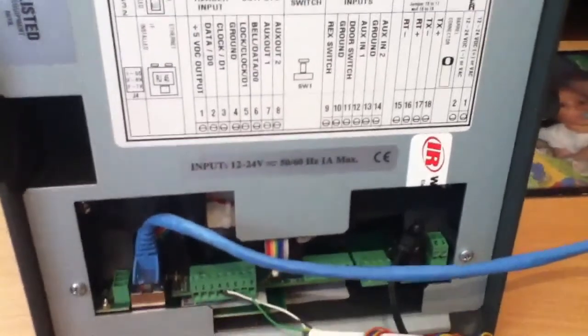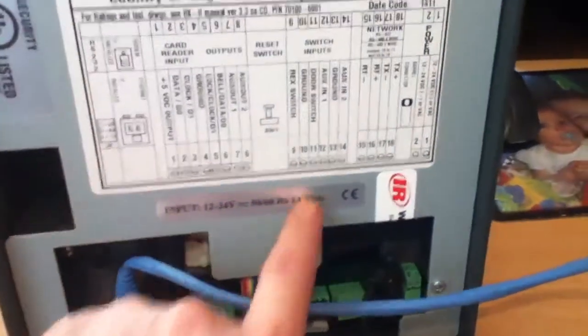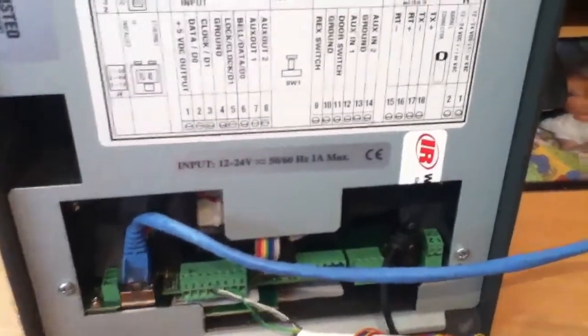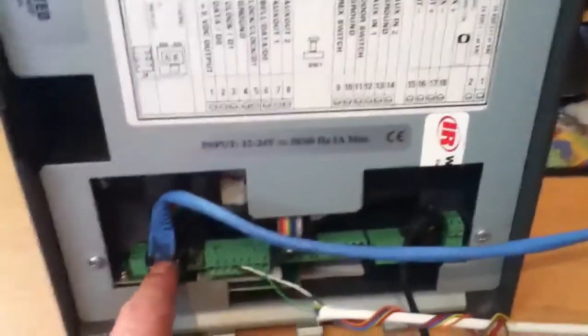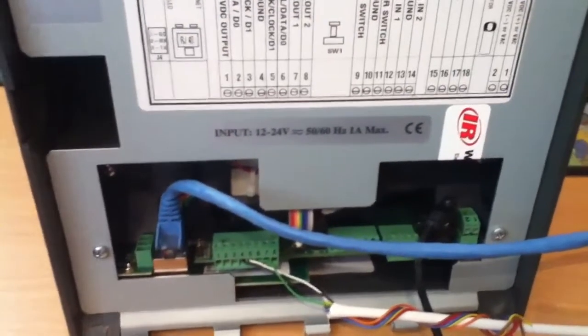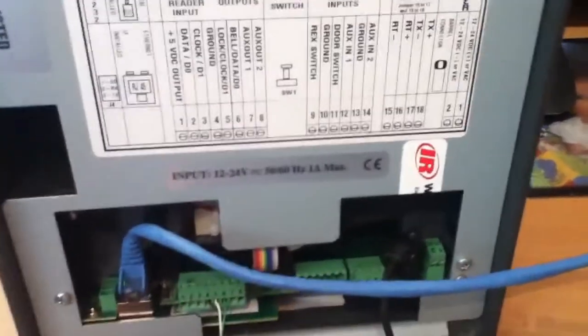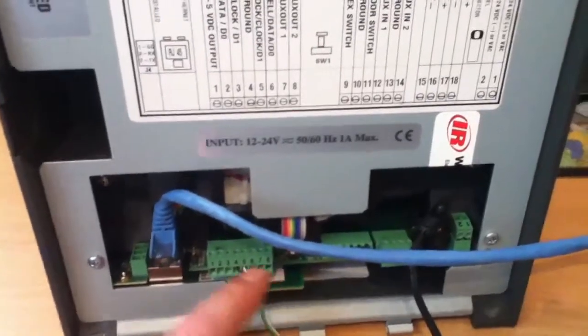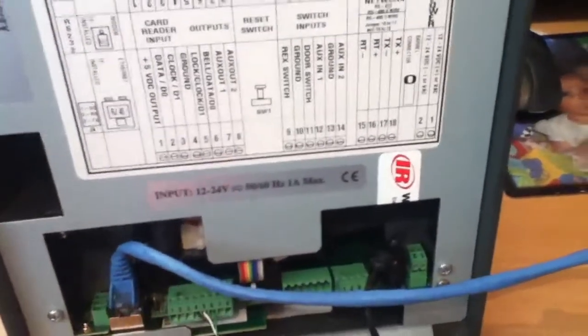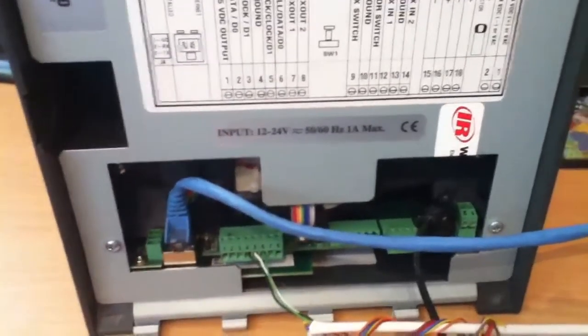This bottom board, this whole plate at the back, can come off with the screws around the sides. Then this bottom board can just slide out, and then you can just plug in this Ethernet module straight into it. Just next to that is our Wiegand data out, and it's been set up for sending clock and data out to the Net2 controller. So it is actually wired into a Net2 controller.